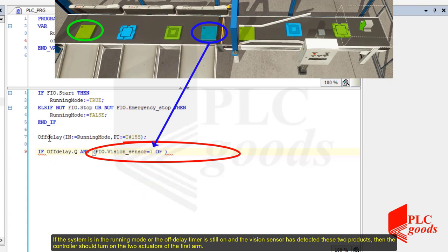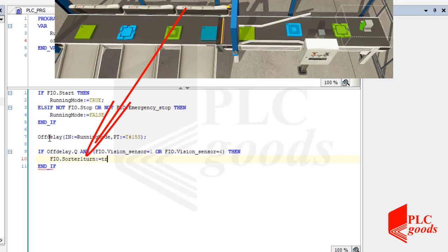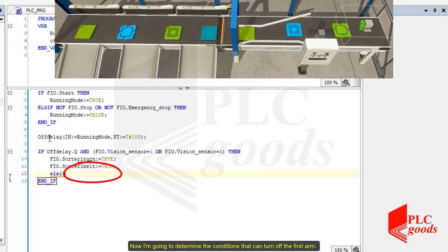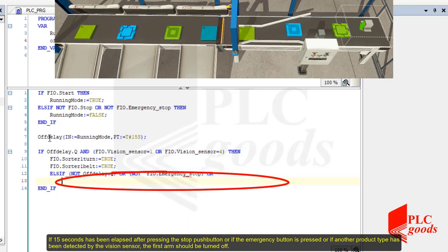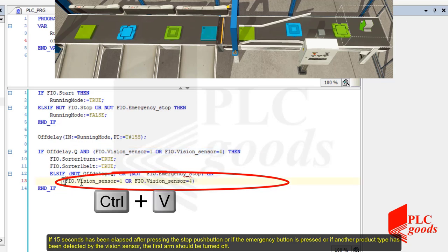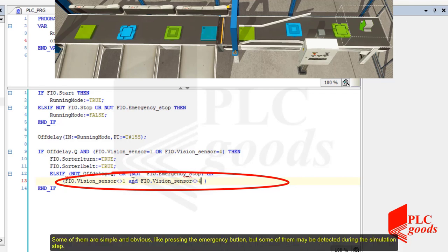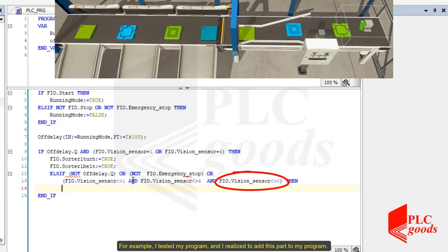Now I am going to determine the conditions that can turn off the first arm. If 15 seconds has elapsed after pressing the stop push button, or if the emergency button is pressed, or if another product type has been detected by the vision sensor, the first arm should be turned off. Note that all conditions that can turn on or off an output should be considered. Some of them are simple and obvious, like pressing the emergency button, but some of them may be detected during the simulation step. For example, I tested my program and realized I needed to add this part.